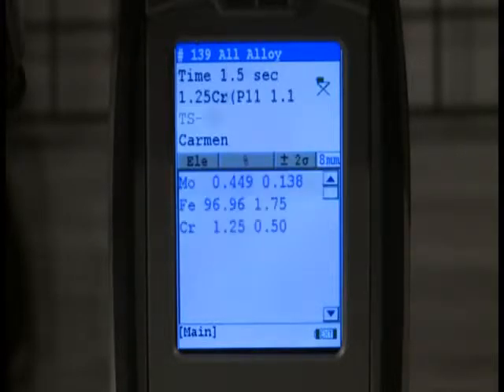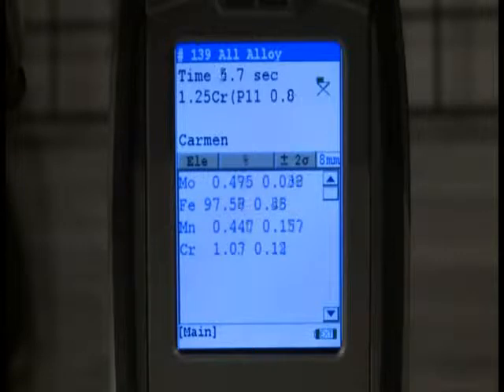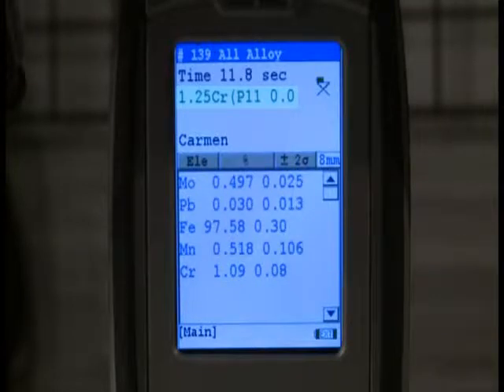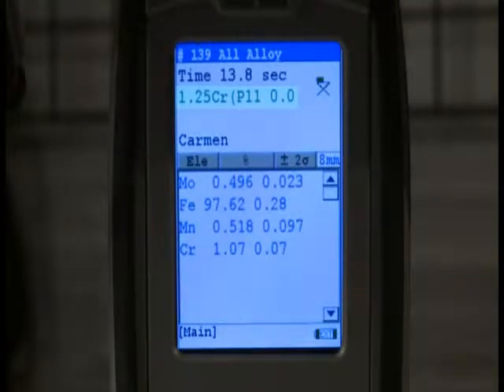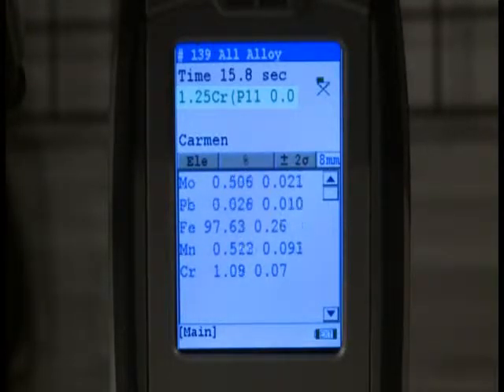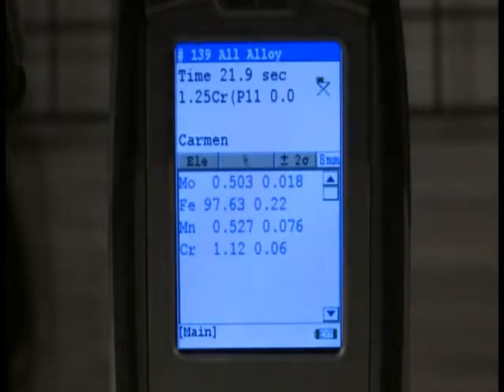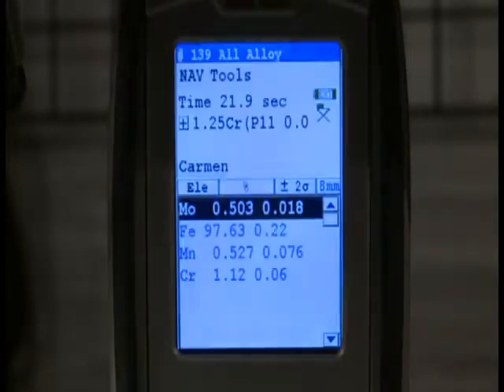When the analyzer has positively identified the alloy grade of the check sample, you will hear a beep from the instrument. When you pass the 5-second mark, you will hear a second beep. This indicates that the typical test measurement time for routine PMI sorting of unknown alloys has been reached. For check sample testing, ignore this beep and continue to hold the trigger for approximately 20 seconds. To terminate the reading, simply release the trigger.